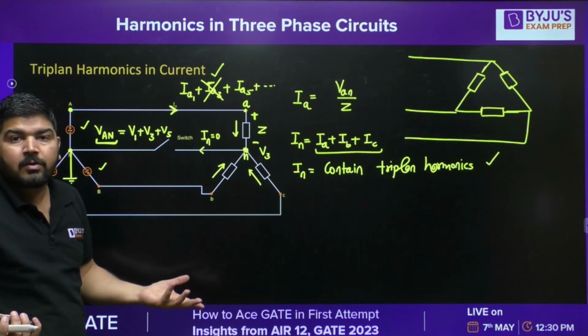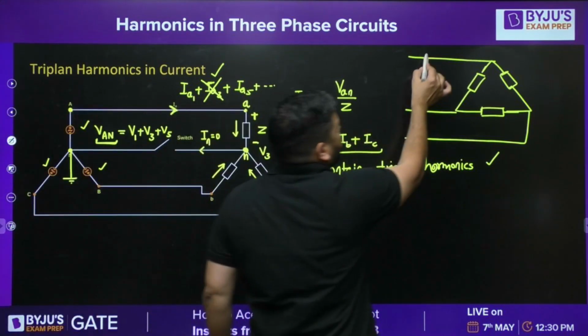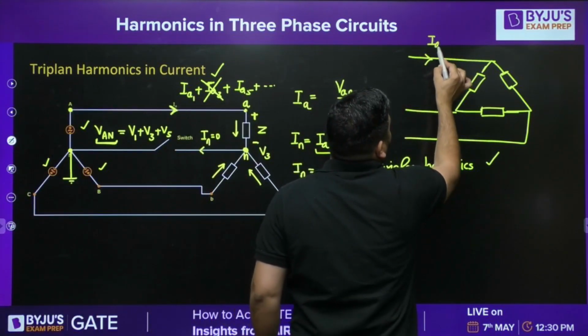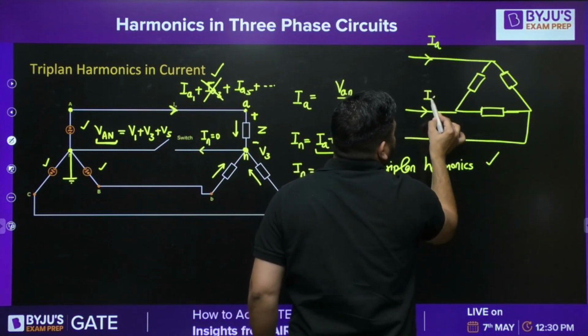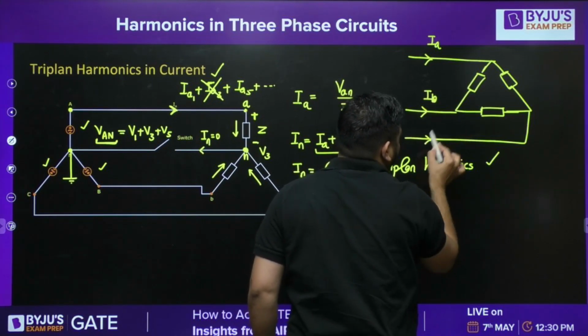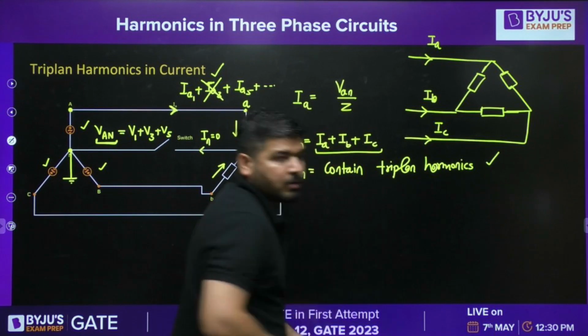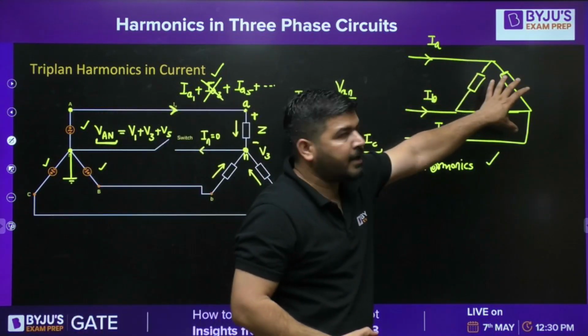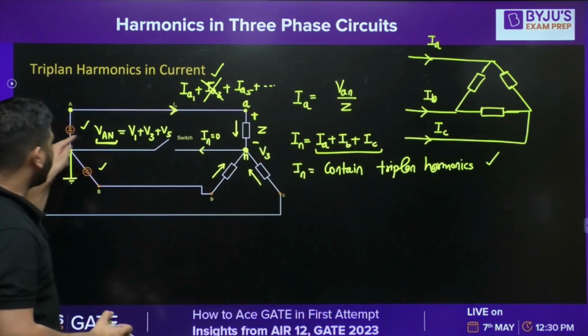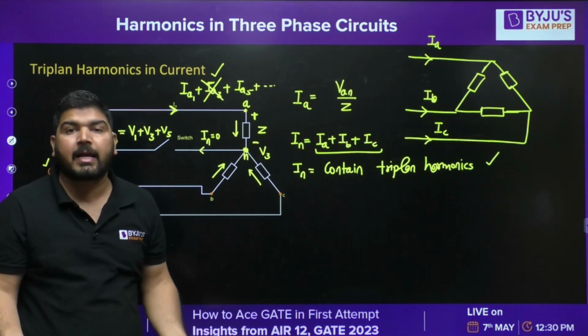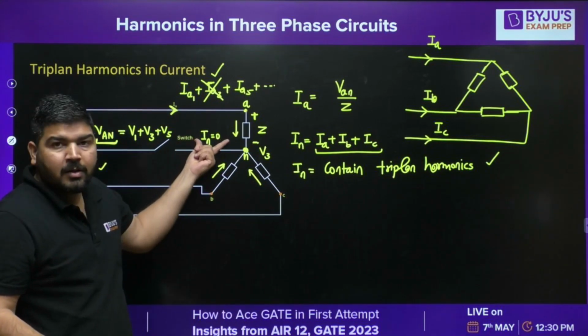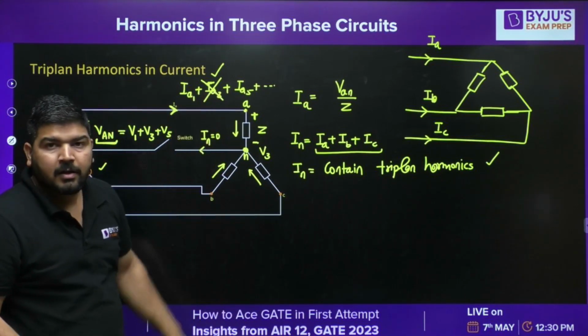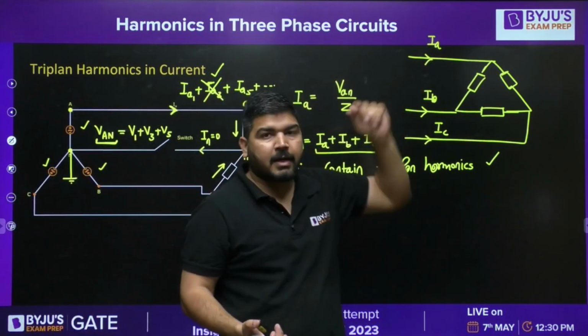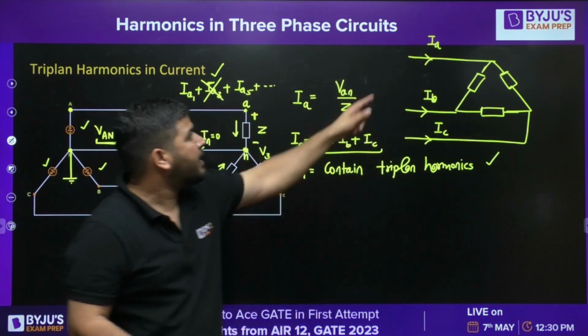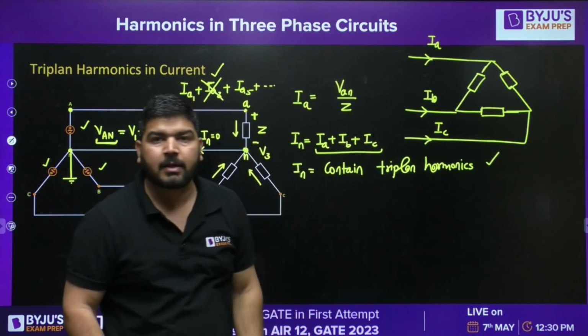The neutral current will only be zero if this line current, or this line current, or this line current doesn't have the triplen harmonic. So in delta, since it is not connected to the neutral of the source, the neutral current has to be zero, and that will only happen if these line currents don't contain the triplen harmonic. So you can say these currents will not contain triplen harmonic.